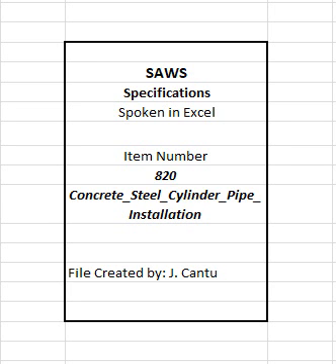20. Pipe cores and coating. A. Review mill certificates for each load of cement for conformance to ASTM C150. B. Perform sieve analysis weekly for each source of coarse and fine aggregate for conformance to ASTM C33. 21. Prior to press dressing, inspect each core for voids, chips, cracks, deleterious surfaces and foreign matter.